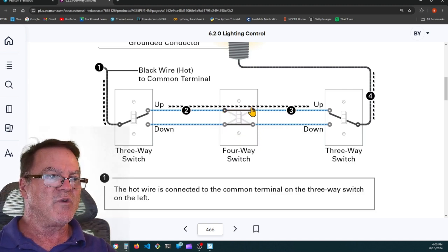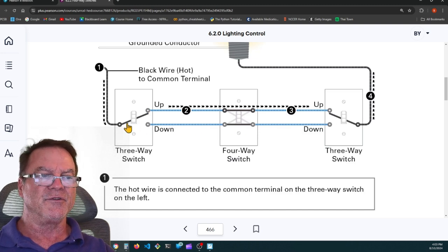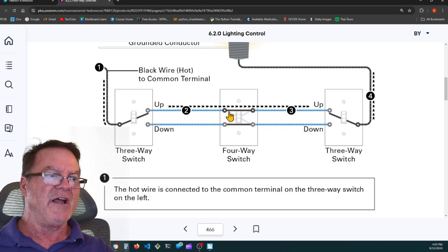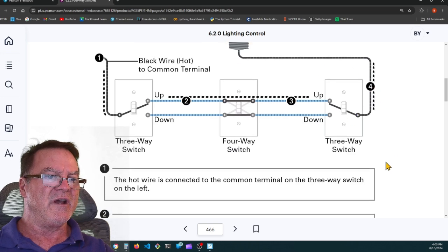If we were to switch this four-way switch, we would go from the parallel configuration to the X configuration. And the current going through this traveler would be going down to the bottom traveler, and it would dead end right here. And the light would not be on. I really shouldn't say current, because when the light is off, there is no current flow. But it's the potential, it's the voltage. The voltage is on the upper traveler, and then it would go down through the crossed travelers or contact bars to the lower traveler, and it would dead end right at this traveler screw. It would not continue on. The light would be off.